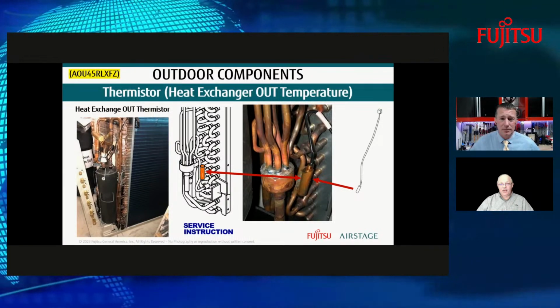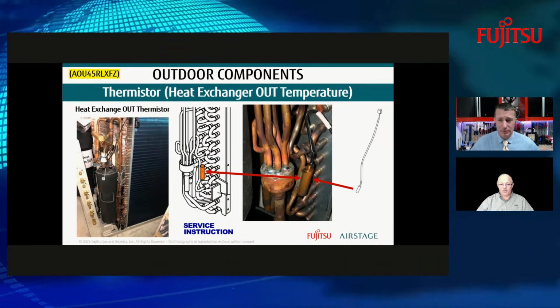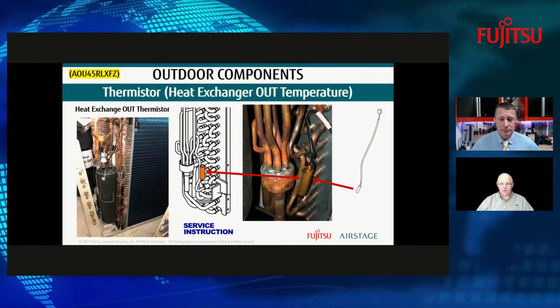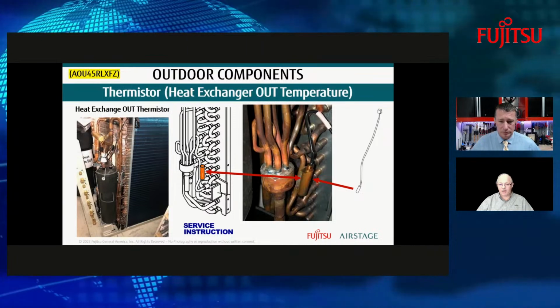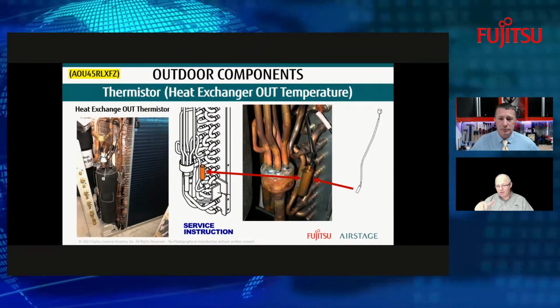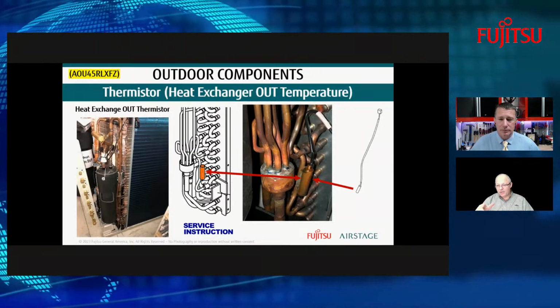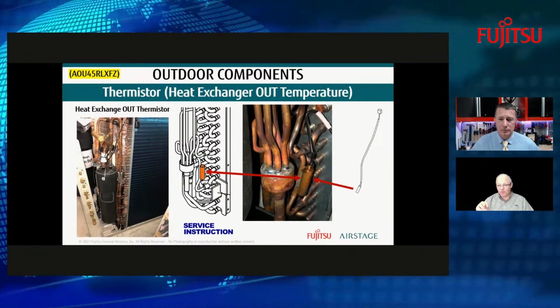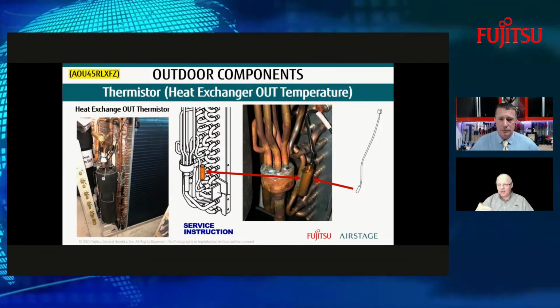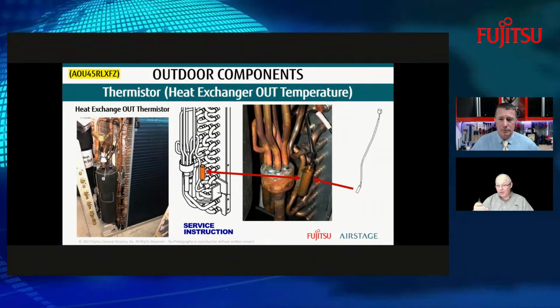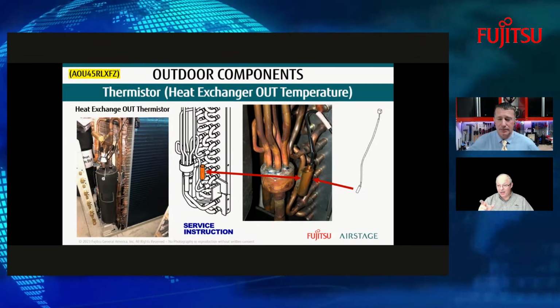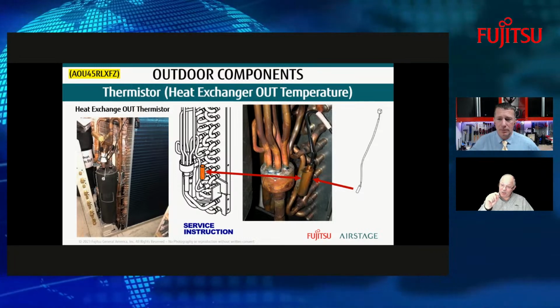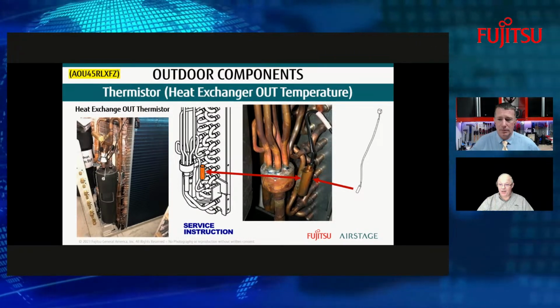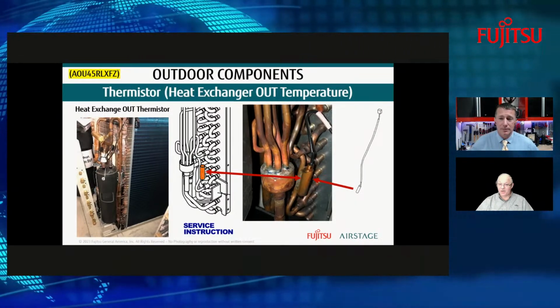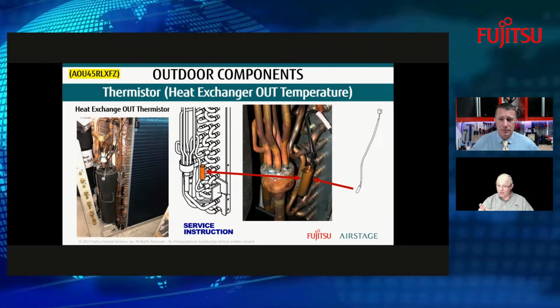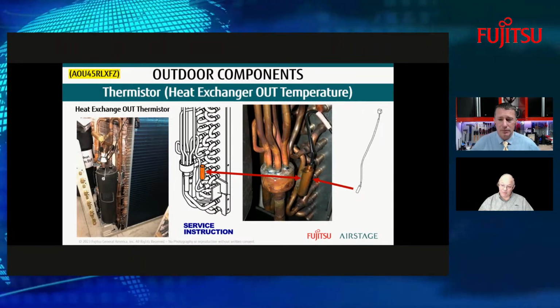Very true. Now we get into the heat exchanger out temperature thermistor. So this is looking at the subcooling that's happening through the heat exchanger. Now, if that number is coming back different, what could happen is if it senses a temperature that's not favorable, and the algorithm cannot keep the subcooling in the range it's in, then it's going to send the information back to the outdoor board, and the board's going to say speed up that outdoor fan motor. Okay. So it's still trying to maintain the subcooling, and at the same time, it's trying to get enough heat.